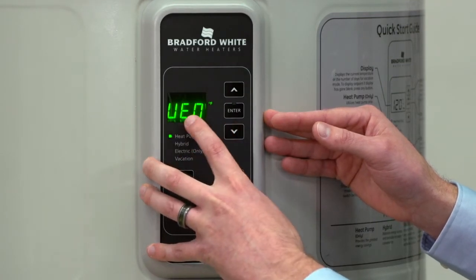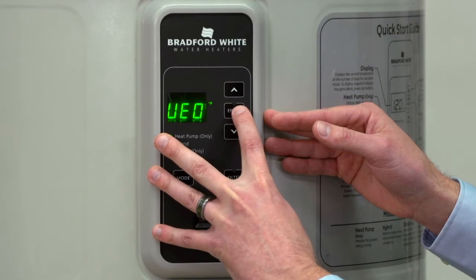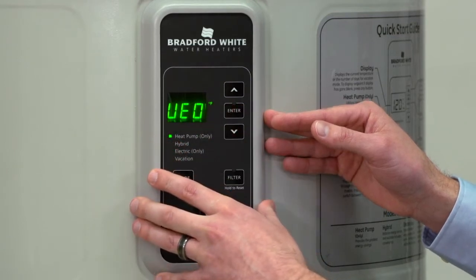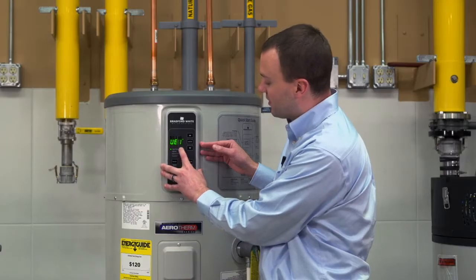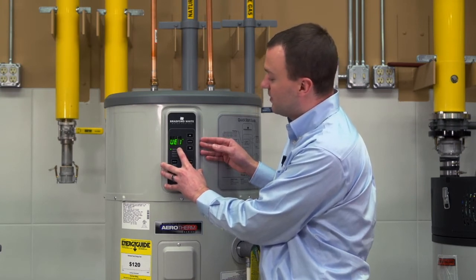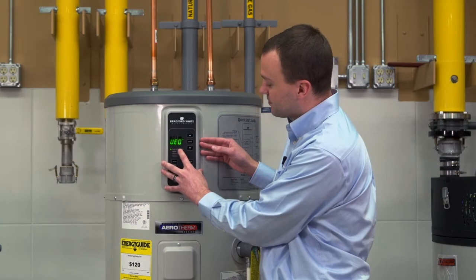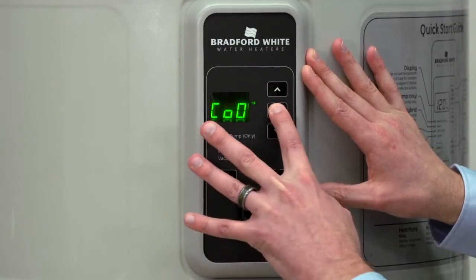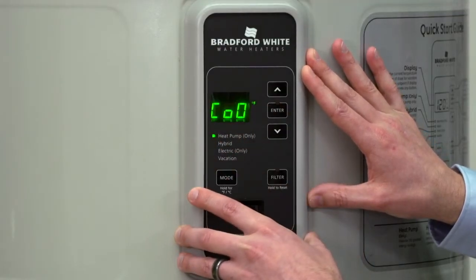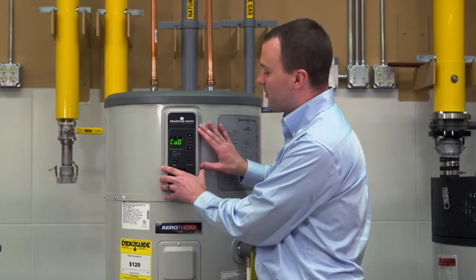So again, we see upper element off. We'll hit enter to engage the upper element. We'll see the 1 come up. We now know the upper element is engaged. We'll turn the upper element off. The next setting is going to be the compressor. We'll turn that on. Again, remember we're turning on a component.